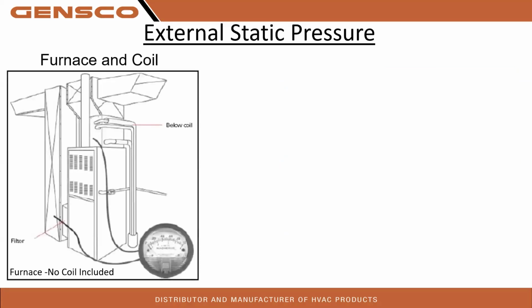External static pressure. Here's some outdated pictures. That looks like a really old furnace. Yeah, we need to update these. But this gets the example in there, right? So let's pull the furnace filter out. We can put the filter back in too if you want to know the static pressures or that pressure drop across that filter. But we want to take the rating across just the furnace.